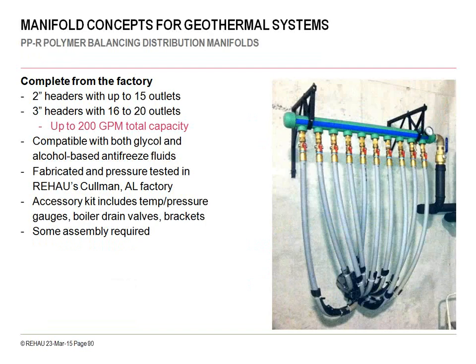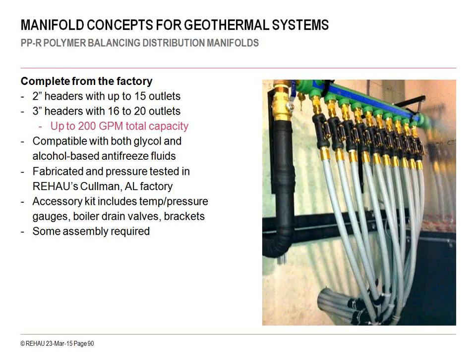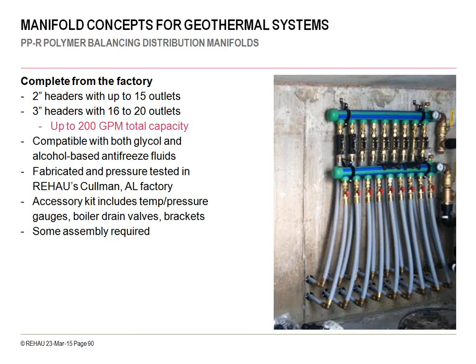and then mounting brackets. And here's some images inside a mechanical room of headers that have the polyethylene flow gauges, and here you're seeing the pair of them, and a supply drop and a return drop would be representative, in this case, of a circuit that would have the ability of controlling a single borehole. And again, we put all this money into these outside geothermal heat exchange fields, and we feel it's very important to have access to the field and have control of the field. If you're ever needing to, in this case, you can isolate down to a single borehole.